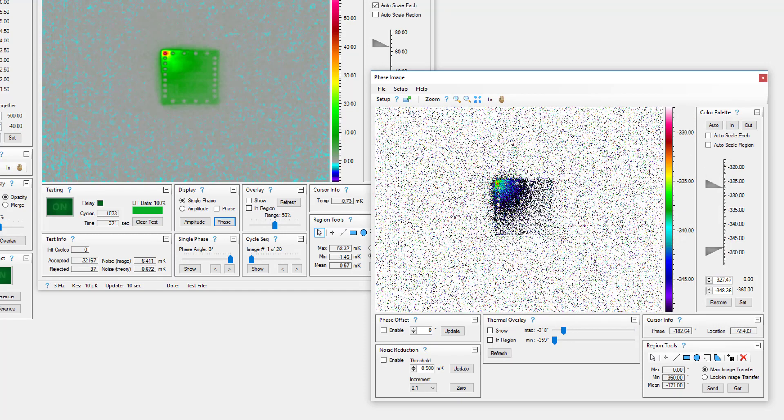When plotting multiple phase depth relationships on a device, it may be helpful to zero the phase of a heat source at a specific depth. This can simplify the depth calculations of other heat sources on the device. To zero the phase, enter a phase offset value that results in a phase value of zero.